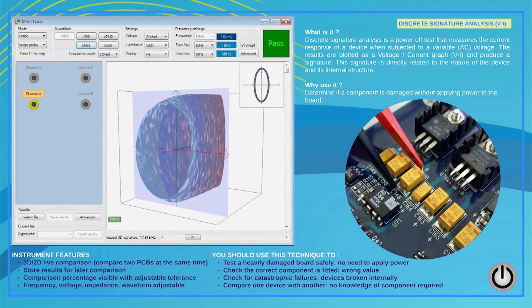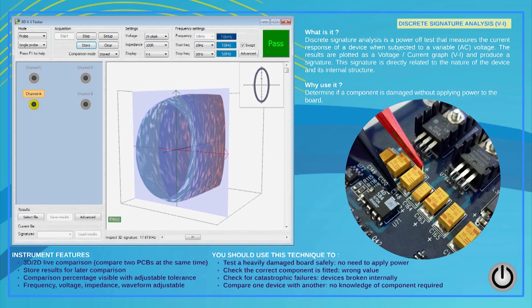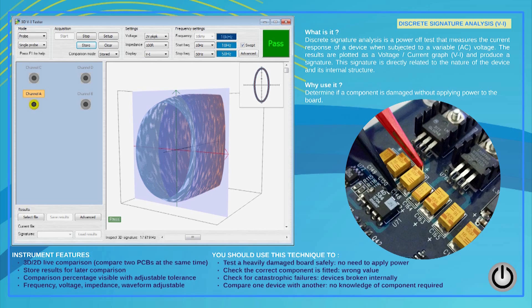The signature analysis test is the most common and safest way of testing devices and PCBs without power. An AC signal is applied to a device and the current response with reference to ground is measured and plotted as a voltage against current graph producing a signature. This signature is specific to the device or test point and will reveal different types of faults such as leaky capacitors, shorts, broken tracks, internally damaged devices and more. The System 8 range offers the unique ability to automatically vary the output signal frequency whilst measurement is taking place. The result is plotted in 3D, demonstrating the impact of the frequency on the device under test. Several parameters can be adjusted and the results from the good board can be stored for later comparison.